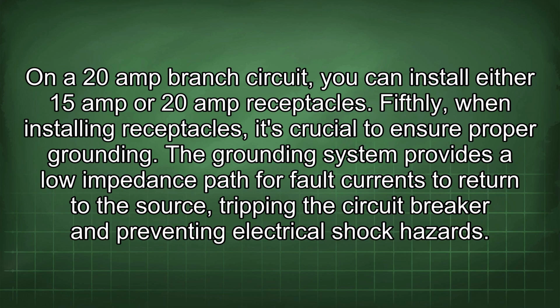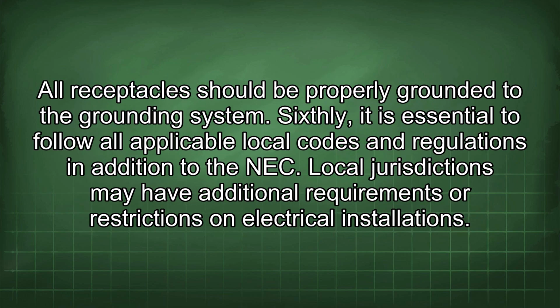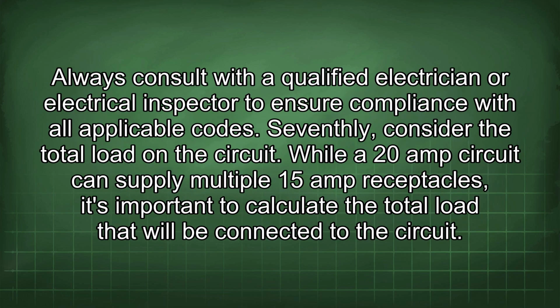Fifthly, when installing receptacles, it's crucial to ensure proper grounding. The grounding system provides a low impedance path for fault currents to return to the source, tripping the circuit breaker and preventing electrical shock hazards. All receptacles should be properly grounded to the grounding system. Sixthly, it is essential to follow all applicable local codes and regulations in addition to the NEC. Local jurisdictions may have additional requirements or restrictions on electrical installations. Always consult with a qualified electrician or electrical inspector to ensure compliance with all applicable codes.